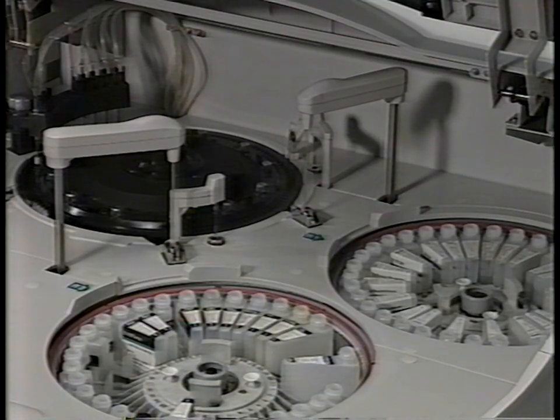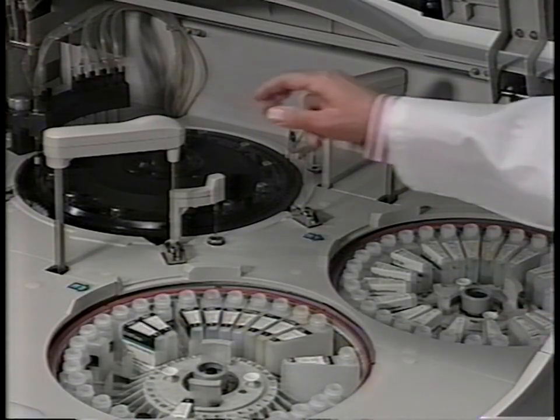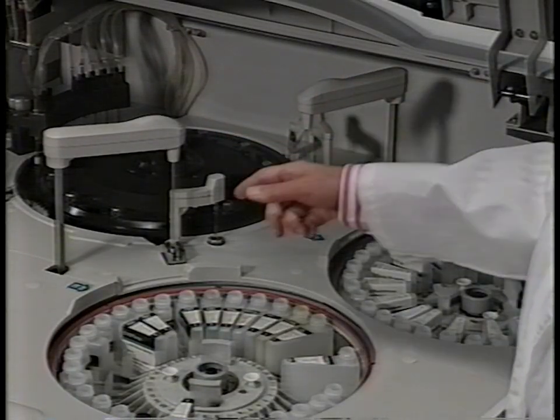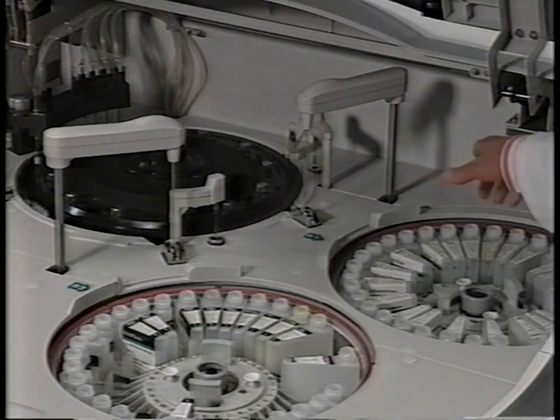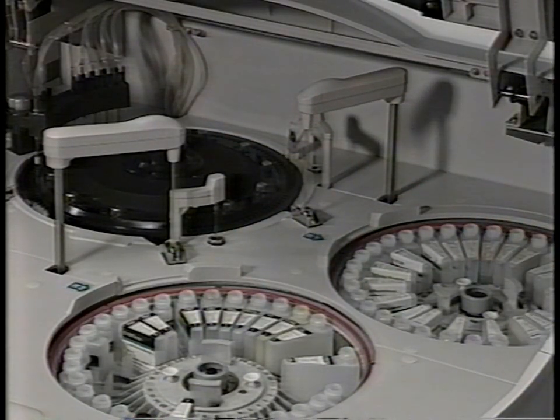Even though there are only 2 reagent probes, each serving 1 of the reagent discs, the analyzer can dispense up to 4 reagents per test. These 4 reagents are dispensed at different times during the analysis process. These times are referred to as T1 through T4. This provides great versatility for current and future testing applications.